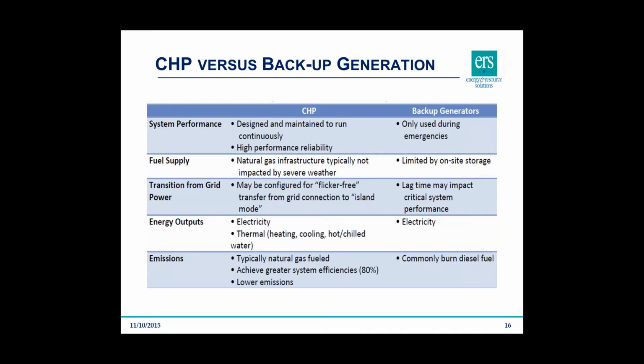From a fuel supply perspective, natural gas is not typically impacted by severe weather, whereas backup generators are limited by on-site storage, and in the event of an extended grid outage or severe weather, it's very difficult to get additional diesel fuel on site. CHP systems are already running all the time, so they can transition flicker-free from grid connection to island mode. They don't need to start up because they're already up and going. Whereas with a backup generator, there's sometimes significant lag time that may impact critical system performance. That could be on the order of seconds, or on the order of tens of minutes to get power back online.